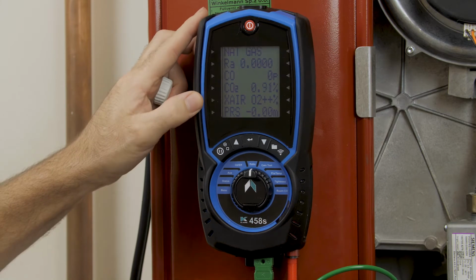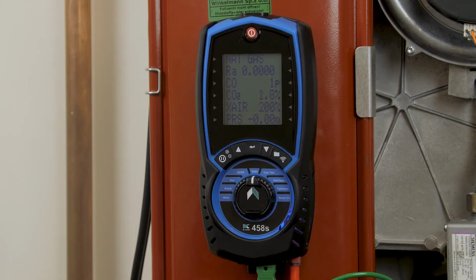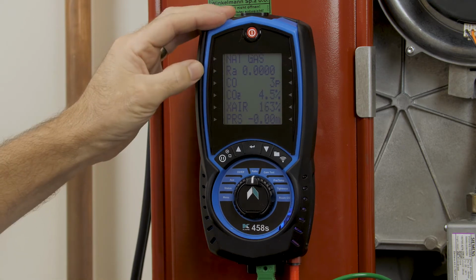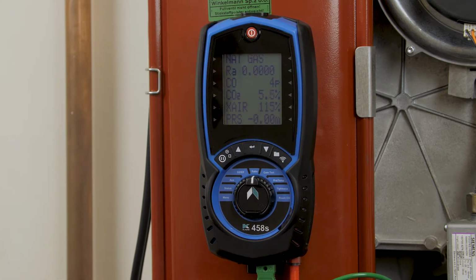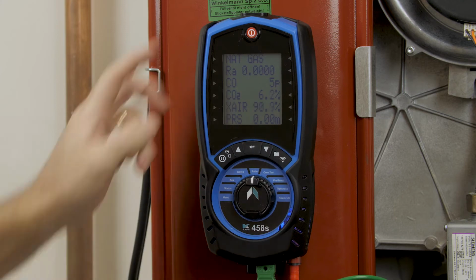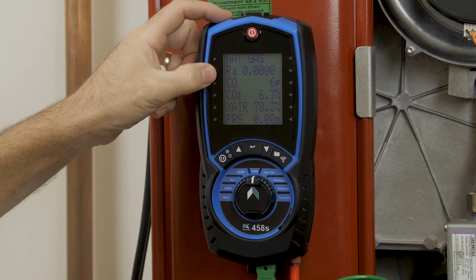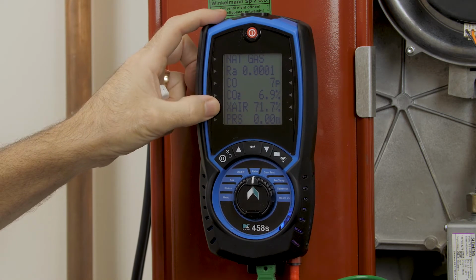Currently the boiler is set to low fire, which is minimum. And as you can see, what we're looking at now is the CO2 starting to rise, and excess air.